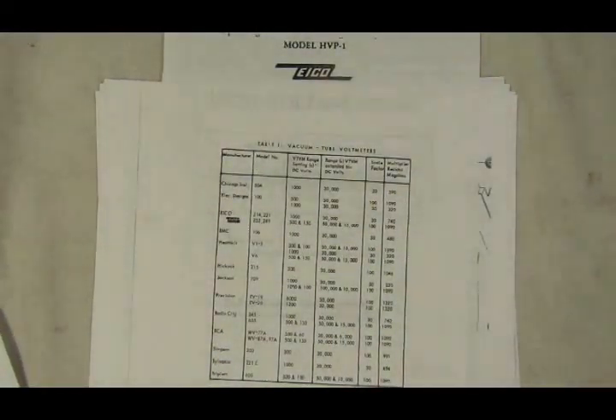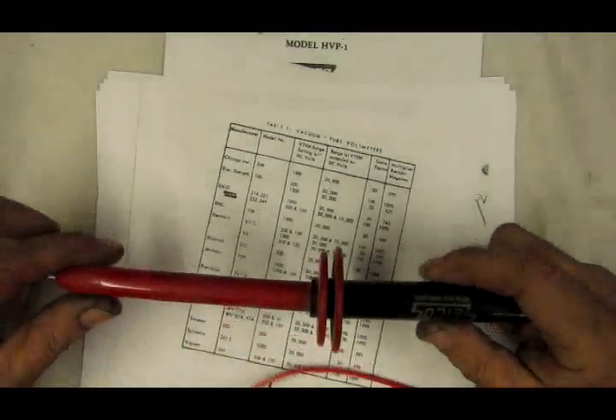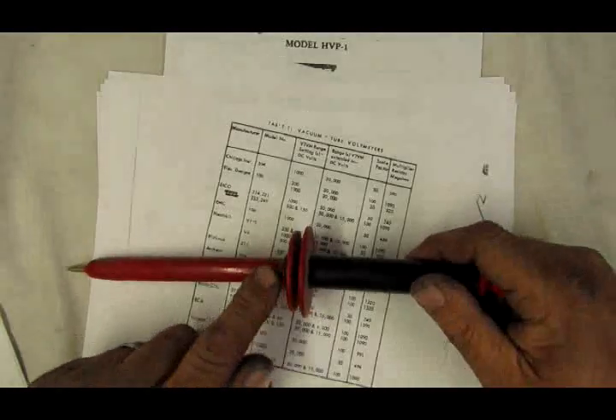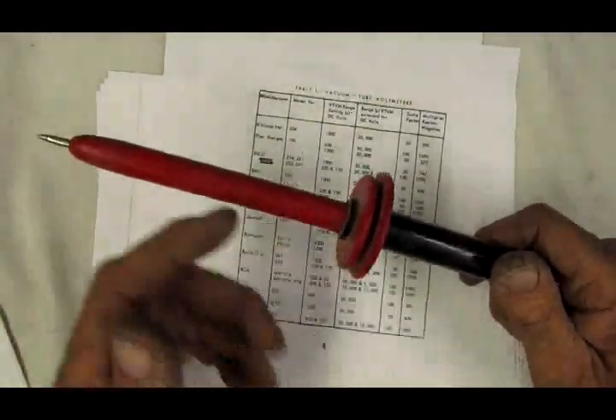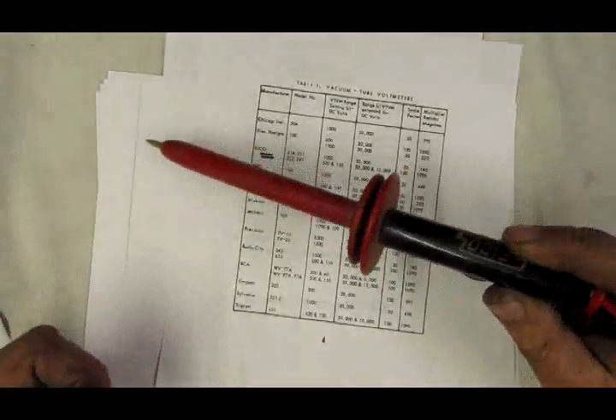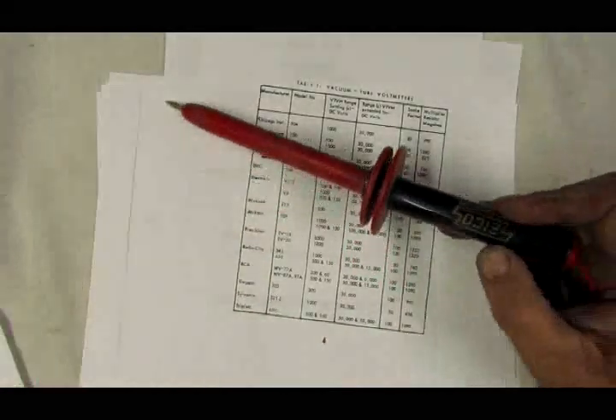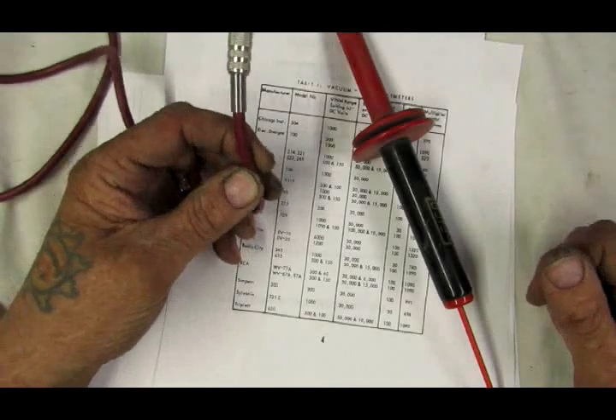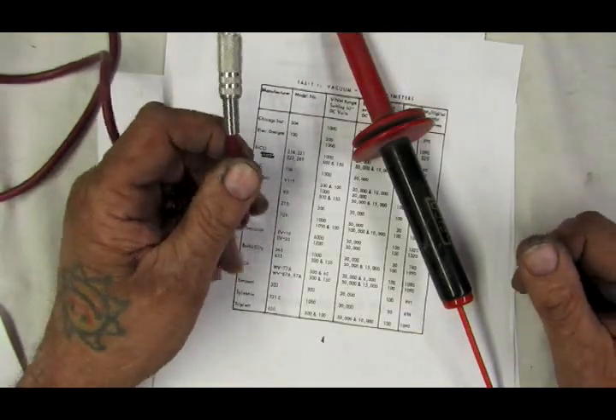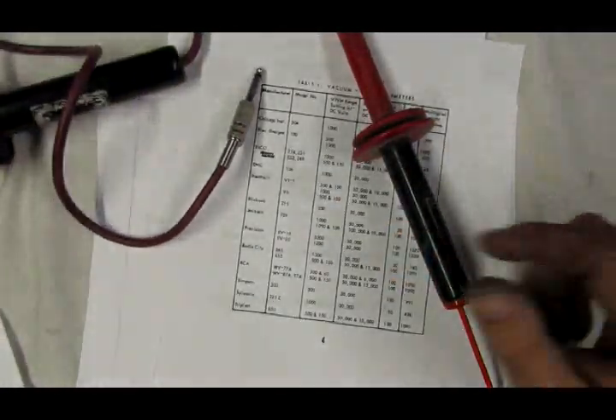Okay, the next one up. This was the first sign that something was wrong. But after double check, this is the HVP2. Only 2 fins. These are supposed to be designed to keep the RF or high voltage from jumping across to your hand. And as you can see, the regular cables, this is one for the voltmeter, they were, gosh, at least a 1/4 inch thick. And I got thinking about this. If you're hooking this into your voltmeter, most of the voltage, if you're measuring, say, 10,000 volts down here, most of that voltage is dropped before it even gets to this cord.